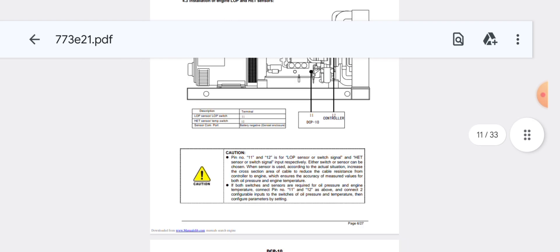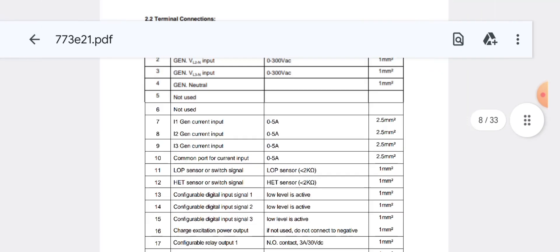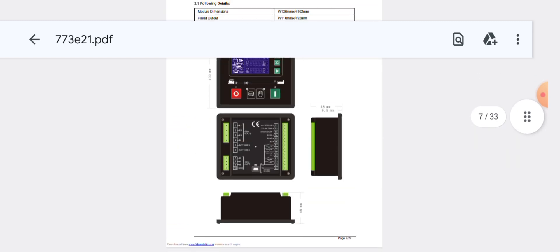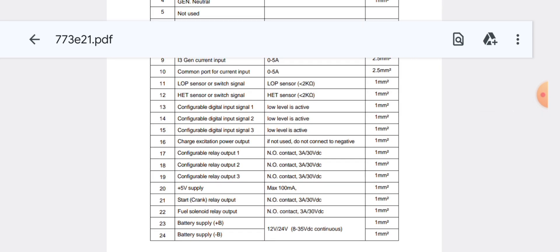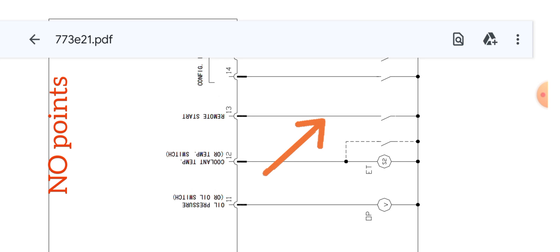Now let's check the remote control. Pin 13 is a configurable digital input — low level is active, 1mm square wire. You can use a ground signal to the remote control. Once the ground signal goes from NC to NO, this will automatically start the generator.